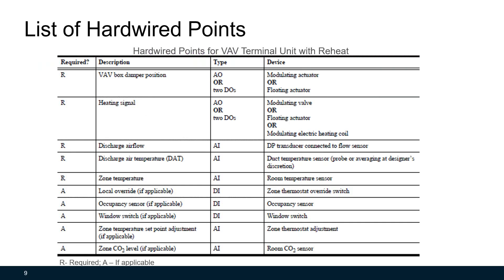The guideline provides a standard list of hardwired control and monitoring points for each of the AHU and VAV terminal unit types. Here is a sample list for a VAV terminal unit with reheat. This list has required points and optional points. Required points include VAV box damper position, heating signal, discharge airflow, discharge air temperature, and zone temperature. The discharge air temperature point is not needed for traditional single-max control logic, but is required for VAV dual-max logic that we will touch on later.